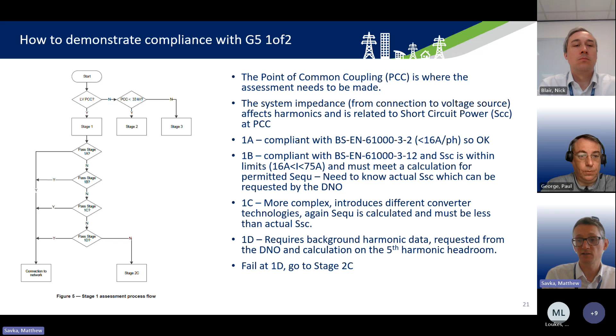Failing 1C, you move on to 1D. This requires background harmonic data. Again, this is requested from the DNO, and I believe there's a fee to pay to get that. And this requires a calculation of the fifth harmonic headroom. And then if that doesn't pass, it goes on to stage 2C. I say fifth harmonic because that's particular to inverter technology. If you've got different types of technology, then it does go on to different harmonics, but that's the main one that we see related to solar PV and batteries.